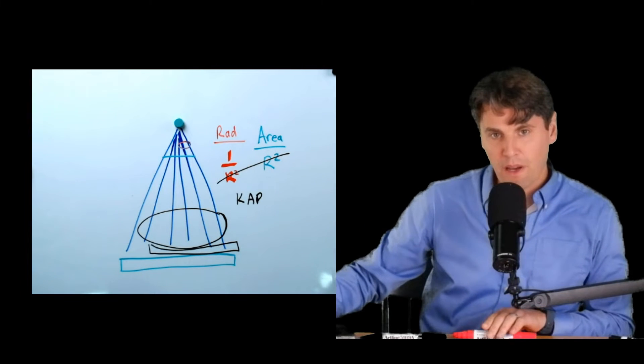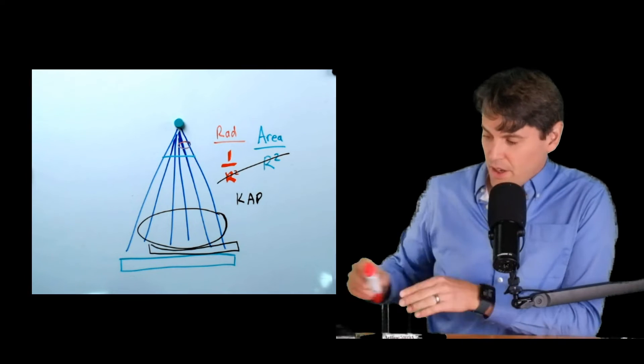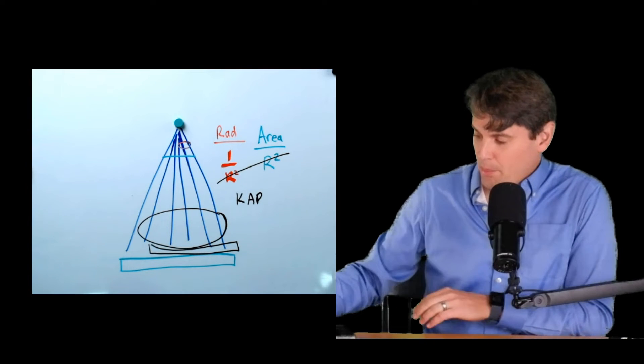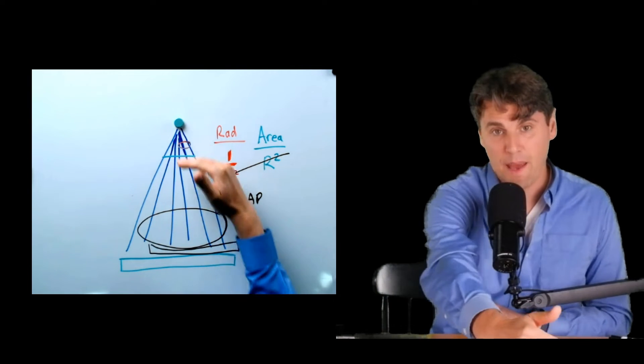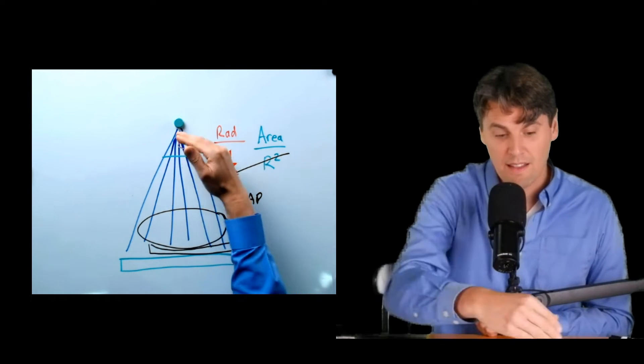So later on, when you're interpreting your Kerma area product, you're going to need to keep that in mind. But for the actual Kerma area product itself, it is going to be independent of the distance from the x-ray tube.